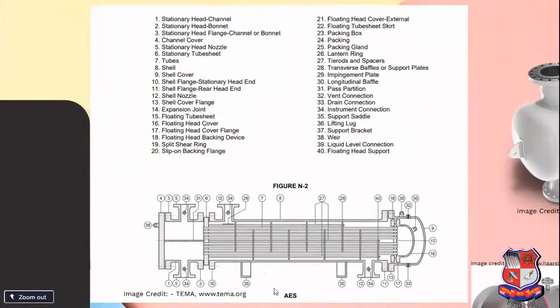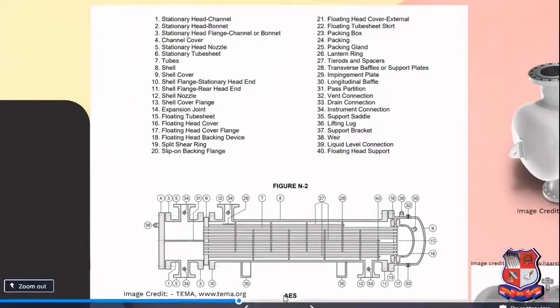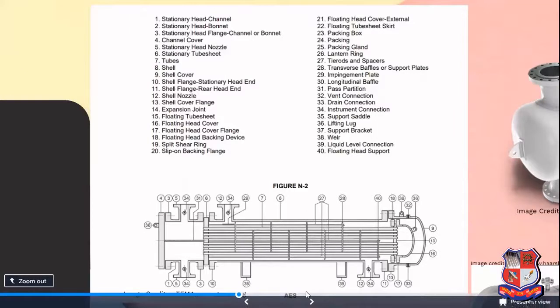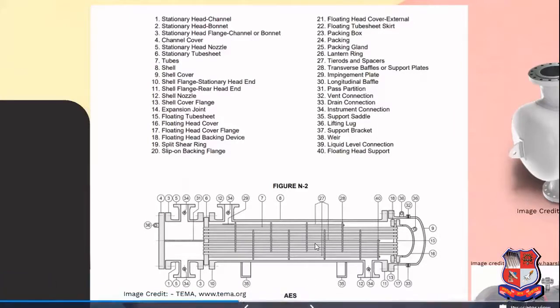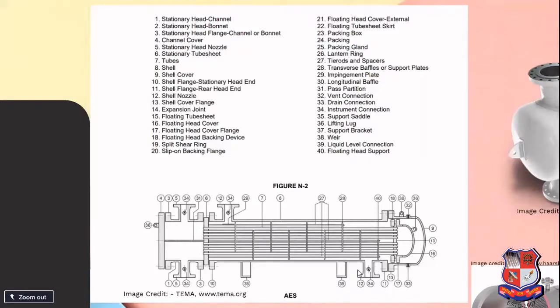Here you are looking at the shell and tube heat exchanger of type AES. You can see clearly this is a cross section of a heat exchanger where there are a total of 4 nozzles. First one for the shell side, then second one again for the shell side, and this is third and fourth. 2 for each side of a fluid. I mean shell side fluid and tube side fluid. These horizontal tubes are the ones through which the tube side fluid passes, and from these nozzles the tube side fluid enters, and from these nozzles the tube side fluid exits.